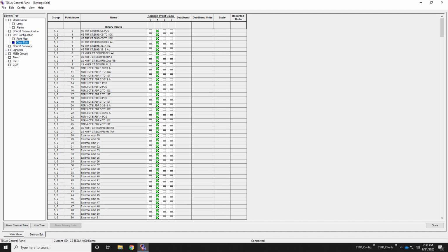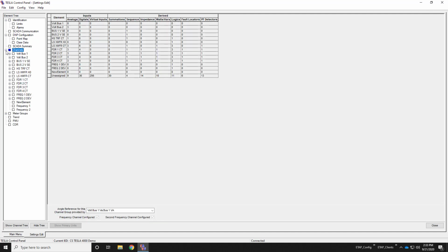Additionally, moving on to the channel section, here we can define all of the different CTs and PTs, basically the devices or measurement points that we're measuring by this fault recorder. Here I have set up a number of different points where I've defined the different measurements, both hard inputs, CTs and PTs, and the derived inputs, calculated values such as megawatts, megavars, etc. All of that is calculated in here.